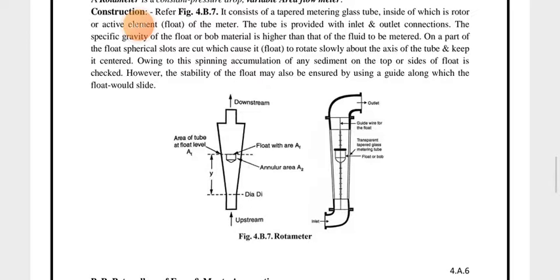As the flow of fluid increases, the float rises by a certain height h from the datum line. The area of the tube at float level is noted. On the right side diagram, a calibrated scale is marked on the transparent tapered glass metering tube. Inside this tube, there is a float or bob, along with a guide wire for the float.